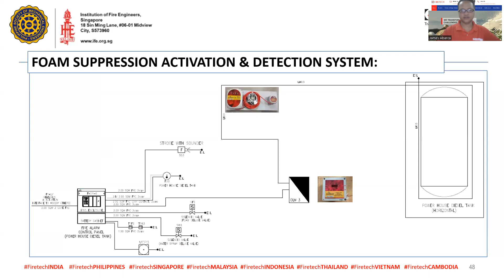So there is a panel, and of course there's a detection. It can be a linear heat detector for zone 1, or you can directly deluge and activate the solenoid for the deluge valve. In this application, I put zone 1 as a linear heat detector, and a UV-IR flame detector as zone 2.